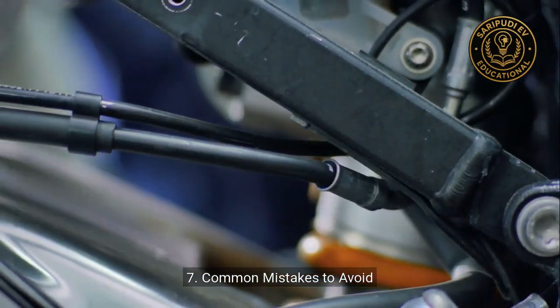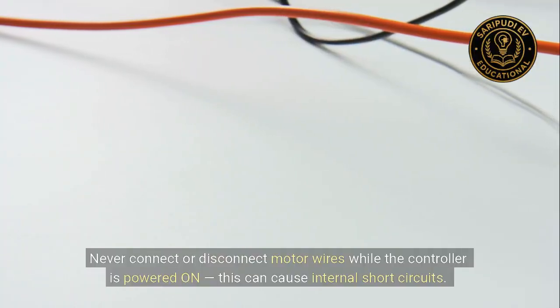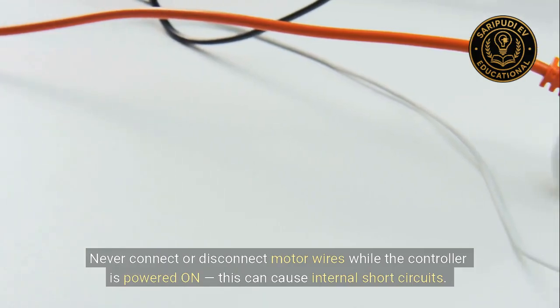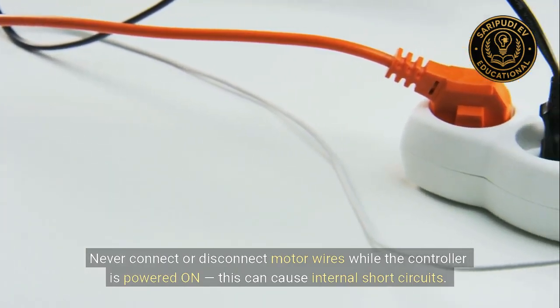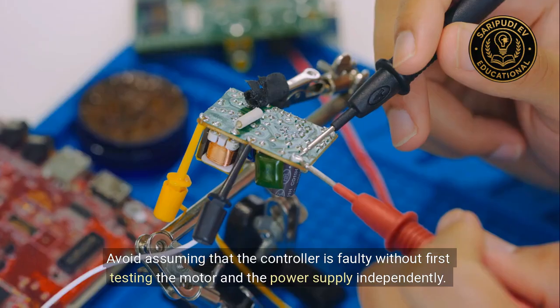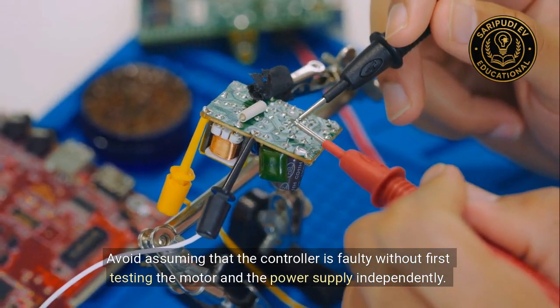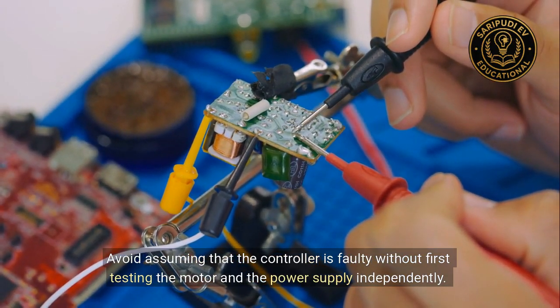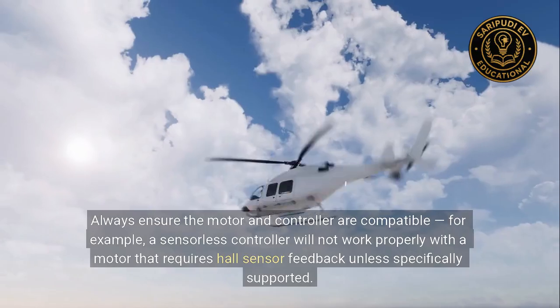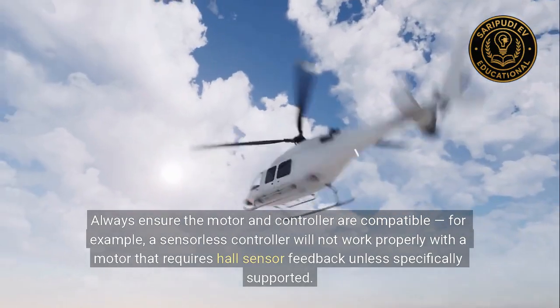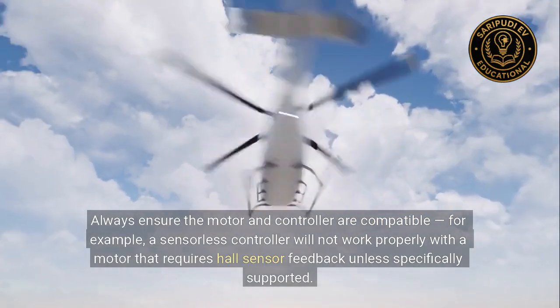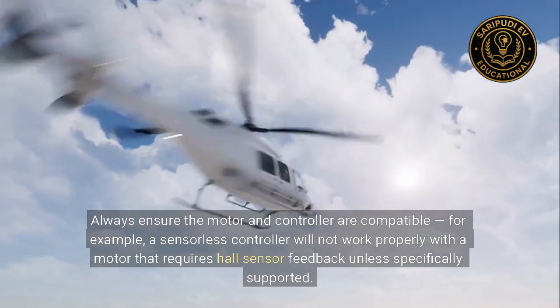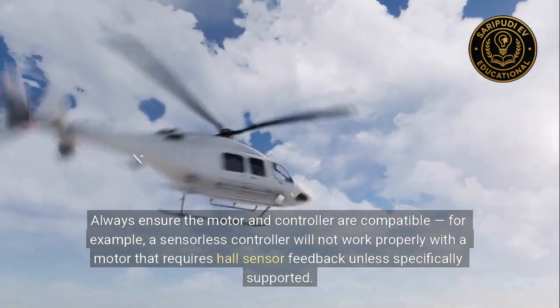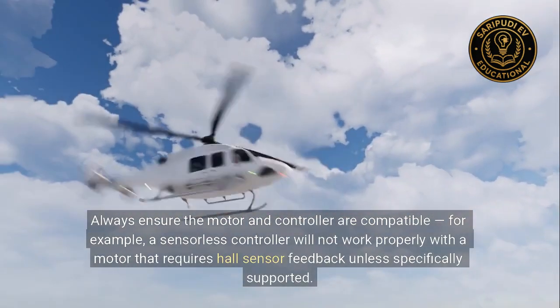7. Common mistakes to avoid. Many failures occur due to common mistakes during setup and testing. Never connect or disconnect motor wires while the controller is powered on. This can cause internal short circuits. Avoid assuming that the controller is faulty without first testing the motor and the power supply independently. Always ensure the motor and controller are compatible. For example, a sensorless controller will not work properly with a motor that requires Hall sensor feedback unless specifically supported.